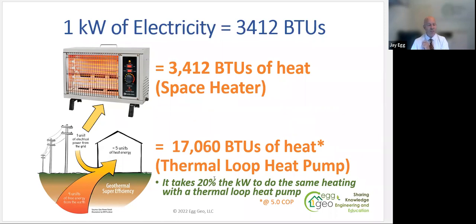It takes 20% of the kilowatts to do the same heating with a thermal energy network, and that's at a 5.0 coefficient of performance. How do we figure that out? For 1 kilowatt, you get 5 kilowatts out. That's very simple - that's the coefficient of performance.